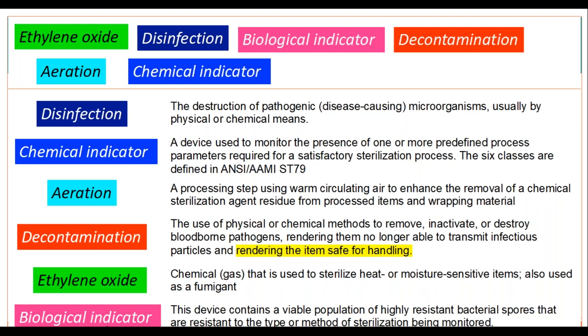Now, biological indicators — remember, this is the one you do not want to confuse with the chemical indicator. A biological indicator is a device that contains a viable population of highly resistant bacterial spores that are resistant to the type or method of sterilization being monitored. The word 'bio' means life — something living. So you're using a viable population of bacterial spores for biological indicators.